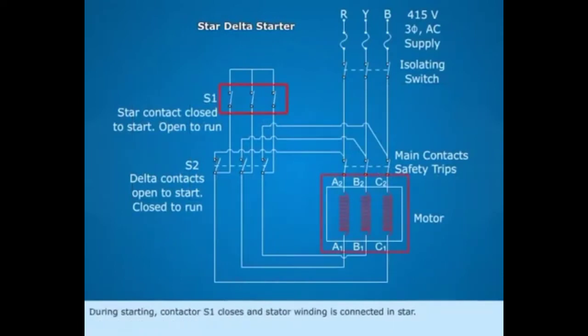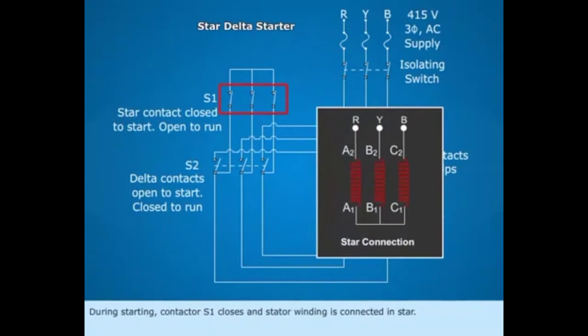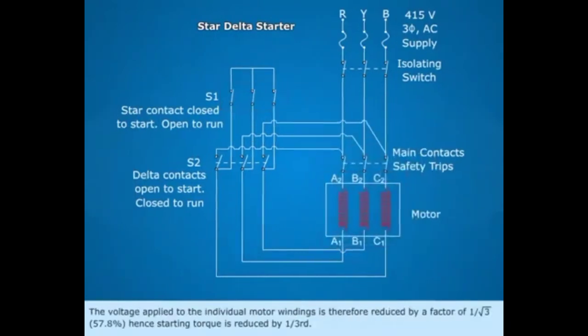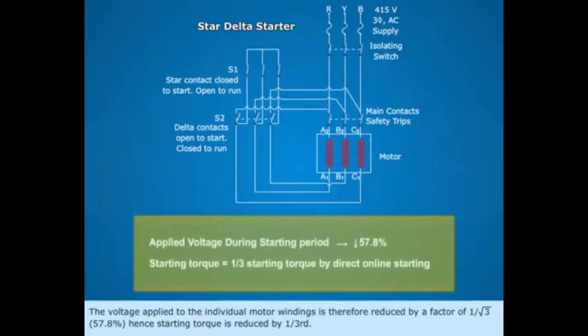During starting, contactor S1 closes and stator winding is connected in star. The voltage applied to the individual motor windings is therefore reduced by a factor of 1 by root 3, 57.8%.